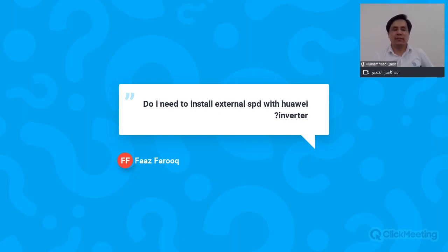Fast Farouk is asking, do I need to install an external SPD with a Huawei inverter? Huawei inverters have a built-in SPD. As such, you will not need to install any external SPD unless your local authority requirement says so. Let's suppose the DC cable length is up to 100 meters, then you must use an external SPD as well with the inverter. So such a requirement is not on the inverter side, but if there is a requirement from the local authority, then you must use an SPD.